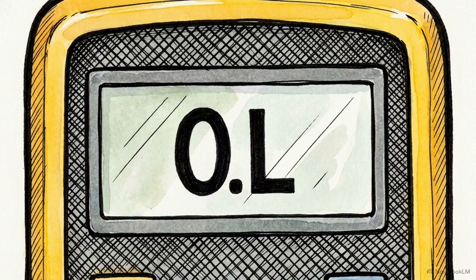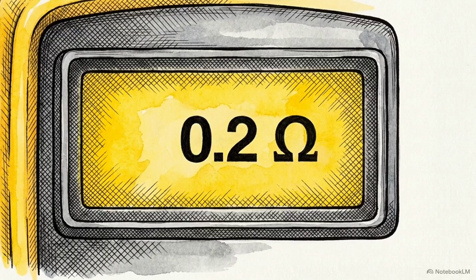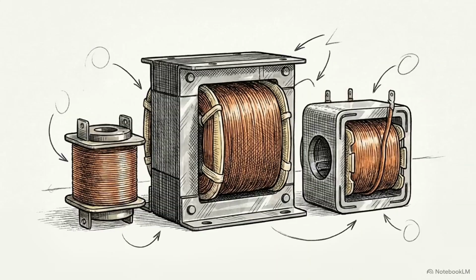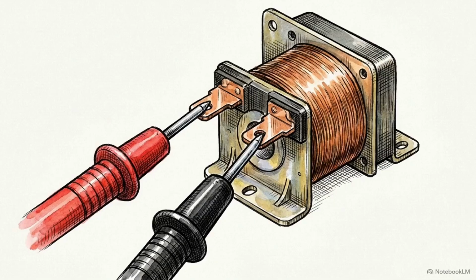If your meter reads OL, that indicates an open circuit with infinite resistance. If it reads extremely low, at or near 0 ohms, you have located a direct dead short. Because normal coil resistance varies significantly depending on the manufacturer and the component design, basic continuity beeps are not enough. Measuring the precise resistance shows whether the coil has failed.